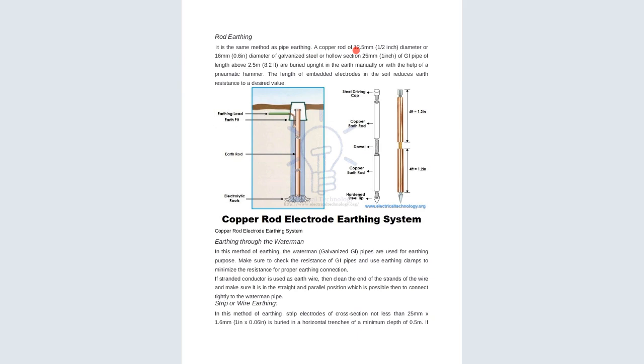A copper rod that is 12.5 millimeters or half an inch in diameter, or 16 millimeters in diameter of galvanized steel, or a hollow section that is a 25 millimeter pipe of length about 2.5 meters, is buried upright in the earth manually or with the help of a pneumatic hammer. The length of the embedded electrode in the soil reduces the earth resistance to the desired value. So this is an earth rod, and the way it is being hit, it is hit down, down, down to the ground until it cannot be seen. Now the copper rod electrode earthing system.